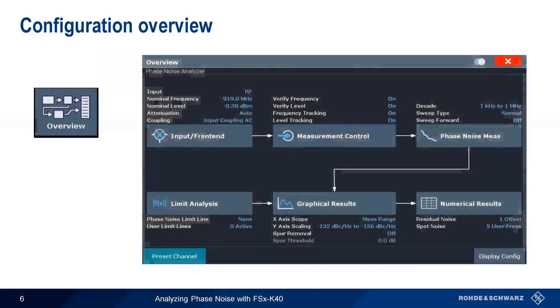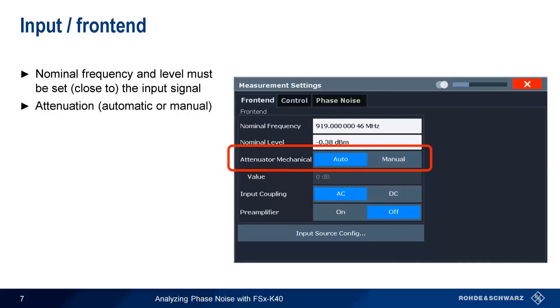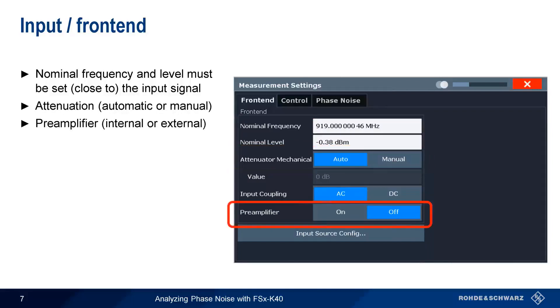The configuration overview is a convenient way to configure measurement setup, analysis parameters, and different ways of displaying results. The most important configuration parameters are the nominal signal frequency and level, found in the input front-end block. In the case of very high input signal levels, manual or automatic attenuation can be enabled; for very low levels, an optional internal or external preamplifier can be enabled. The nominal values should match the input signal as closely as possible, though K40 can also compensate in real time for slight variations in both frequency and level.